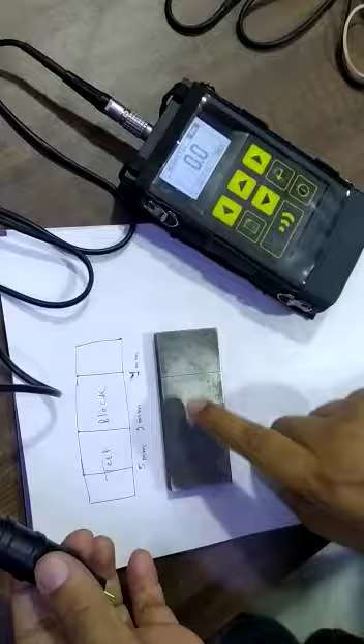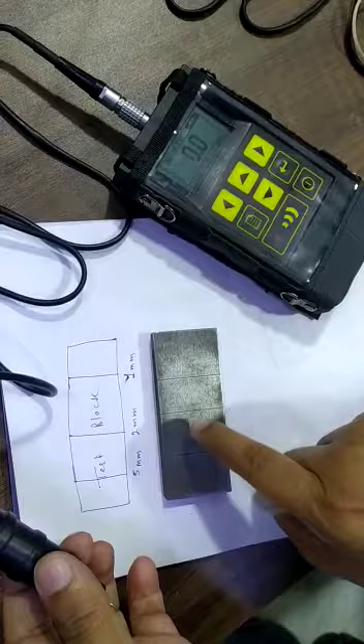I have selected magnetic material and now I will calibrate this machine on the job where we found the crack. This is the sample where we have cracks of depths 1 mm, 2 mm, and 5 mm.